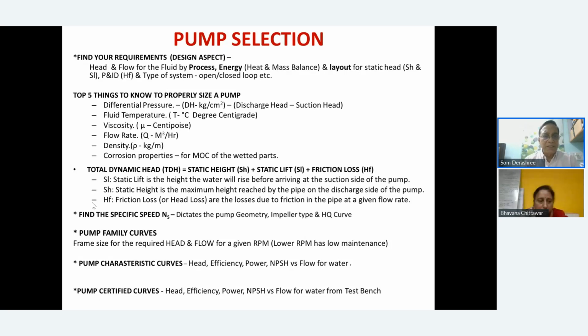So once you know these parameters, then you arrive at the total dynamic head. Now, total dynamic head is basically the summation of the static head, the static lift, and the friction head. Static lift is basically when you have a negative suction. Let's say you are sucking out something from a well, basically. So it has to suck out. So that is the lift. What is the lift till the eye of the pump? That is the static lift.